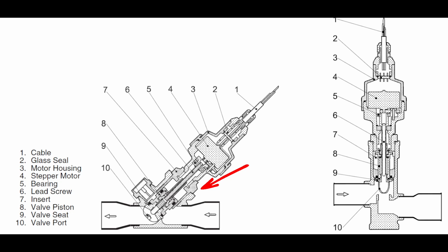Either way, my point there is, just because it's a brand new valve, don't just assume that everything is fine and that it's not having a problem. We always want to make sure that we're testing our calibrations for this. To do that, there's one especially easy way, but there's two ways to go about a calibration check. So the calibration procedure on these is fairly straightforward.